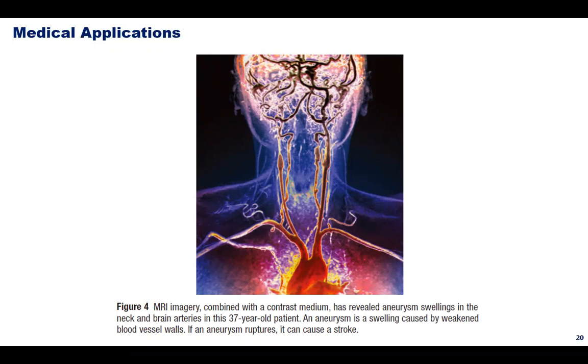The MRI uses a superconducting magnet to create a large, stable magnetic field of approximately 2.0 teslas. The large magnetic field is needed to produce precise images of the soft tissues inside the human body. For an MRI machine to obtain images, a patient must lie on a movable bed that slides into a tube in the center of a magnetic field.